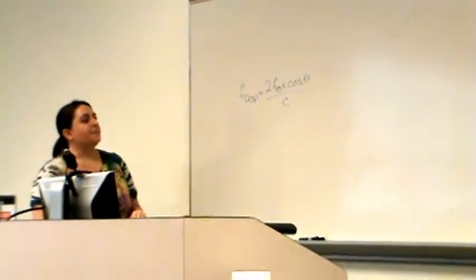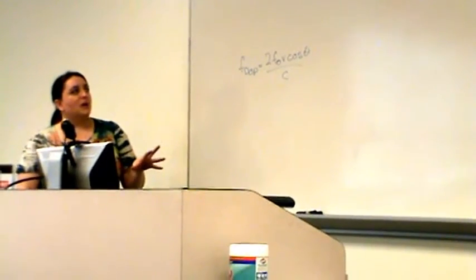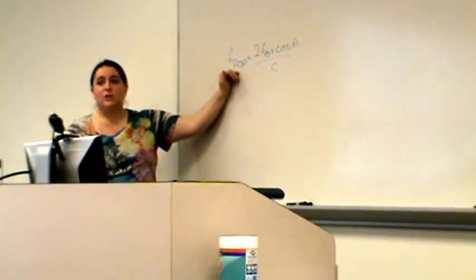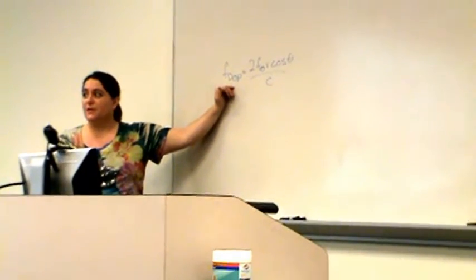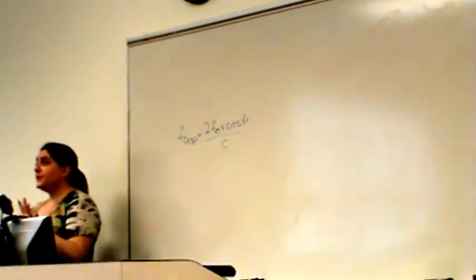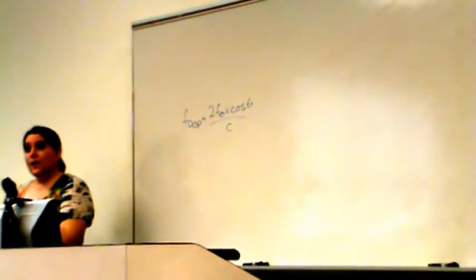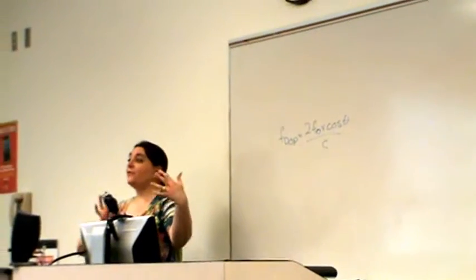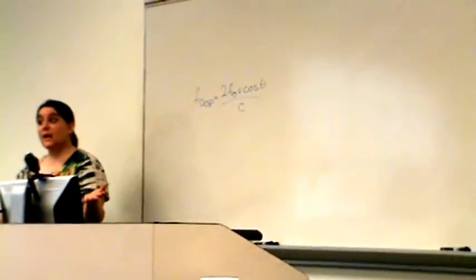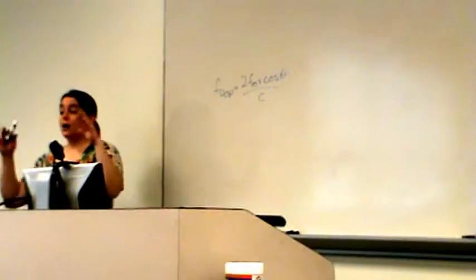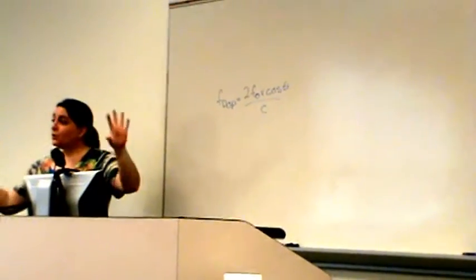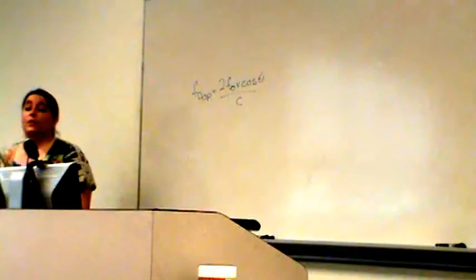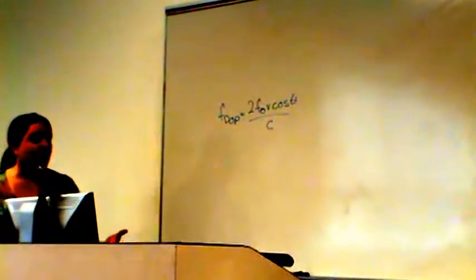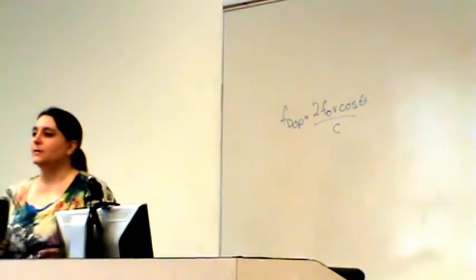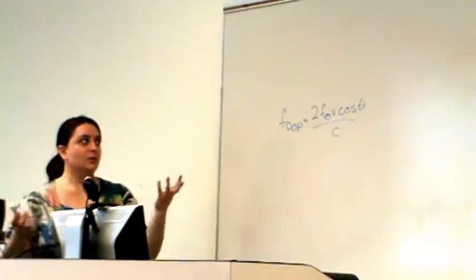All the relationships that are here. And remember when you're looking at this Doppler equation that this is what the machine detects. This is the Doppler shifted frequency. So remember, imaging and Doppler are different. In imaging, we're detecting amplitude changes, acoustic impedance mismatch. With Doppler, we're actually looking at a frequency change. So it's frequency and amplitude. Remember, frequency and amplitude, power are disjoint, there's no relationship. So they're two entirely different ideas. The cool thing about our systems, and what still blows my mind, is that they can do both things at once. It's crazy.